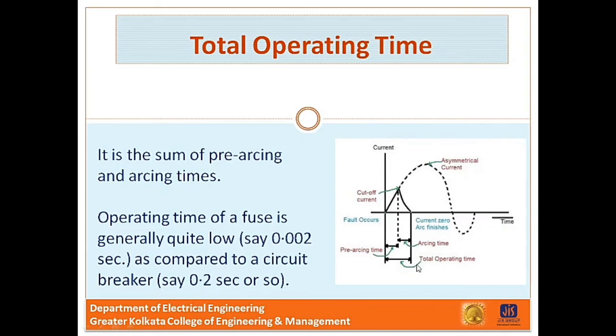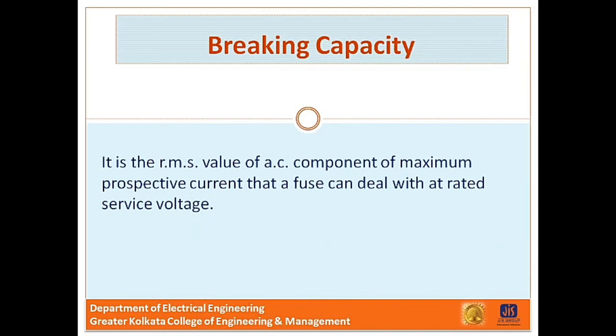It may be noted that the operating time of a fuse is generally quite low compared to the circuit breaker — this is an added advantage of fuse over a circuit breaker. A fuse in series with a circuit breaker of low breaking capacity is a useful and economical arrangement to provide adequate short circuit protection, because the fuse will blow under fault conditions before the circuit breaker has to operate. The last term is breaking capacity: it is the RMS value of the AC component of the maximum prospective current that a fuse can deal with at a rated service voltage.